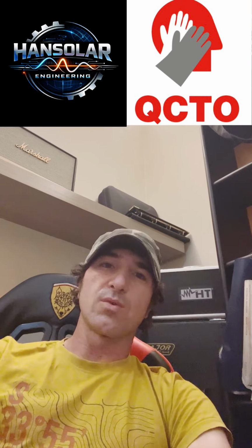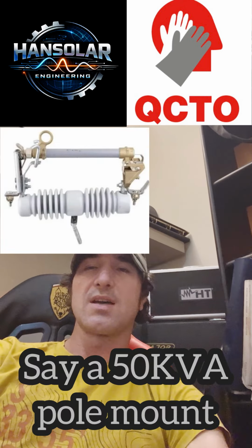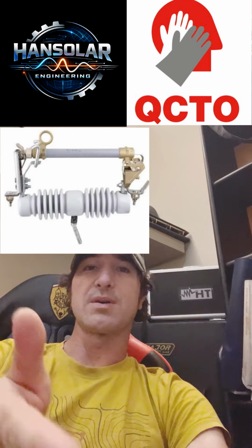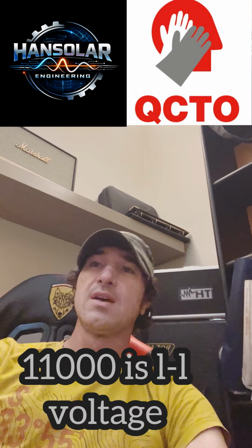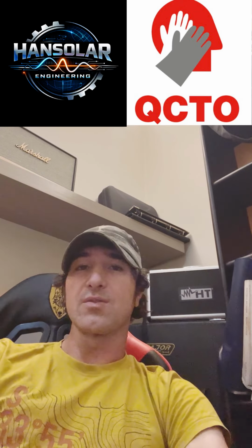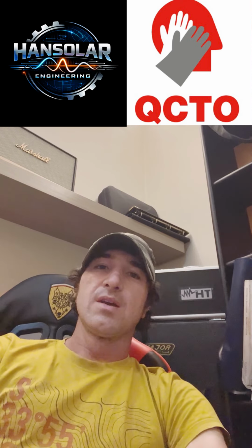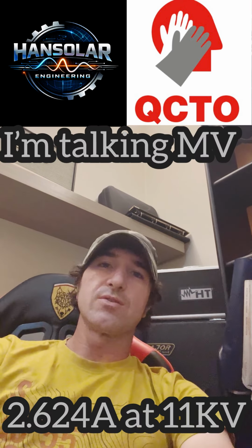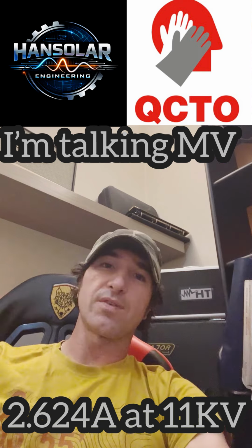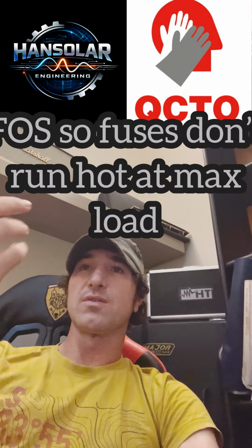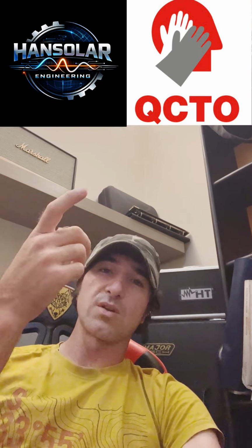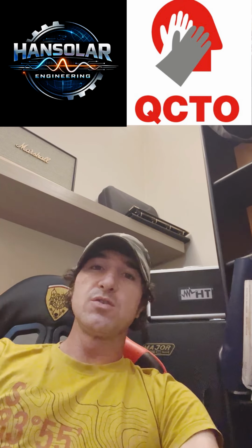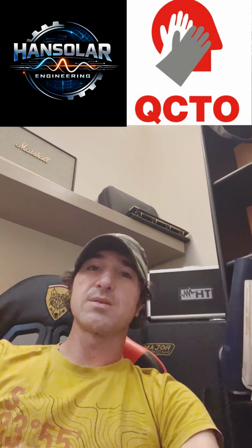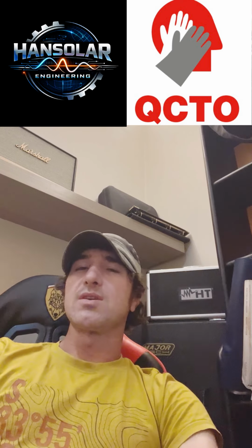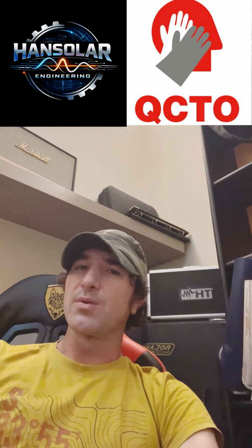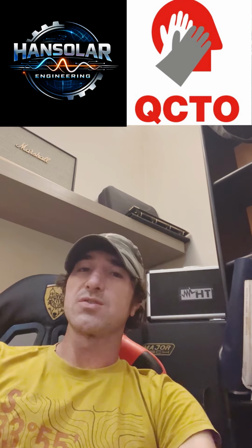But anyway, let's go look at what size fuses you'd be putting on the MV side, right? So you take 50,000 divided by square root 3 times 11,000, and this would give you the amount of line current that you would have in your system. So say it's around 2.6 amps, you take the 2.6 times 1.25 for the factor of 25% overload, or 1.2 if you want 20% overload, and now you have your fuse size ratings, and in my opinion, your maximum fuse size ratings. You can size them smaller, but then you always run the risk of blowing it. So 1.25 is pretty much industry standard.